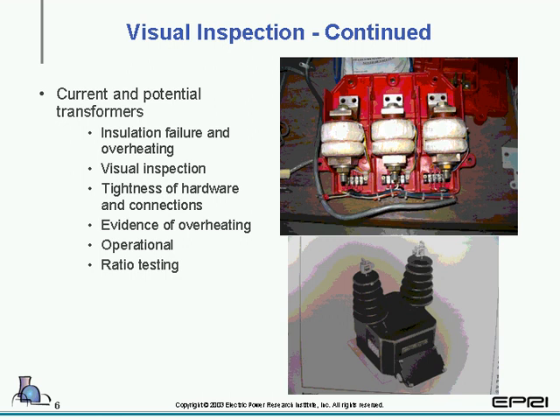Next we'll take a look at current and potential transformers. Visual inspection is usually one of the key items you're going to use when inspecting any type of CT and PT. But there are some tests that can be performed, and we'll be taking a look at those when we start talking about the testing. One of the main ones is ratio testing and continuity.